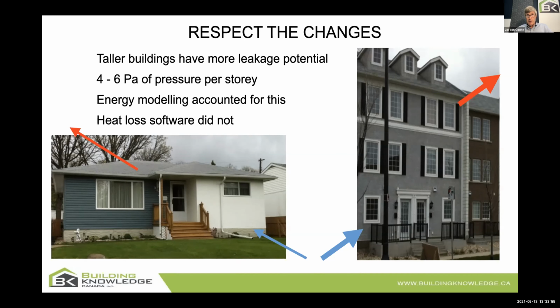Because from a heat loss, heat gain perspective, it makes that building much easier to stay comfortable when I limit that stack effect. And what you need to know is heat loss, heat gain software never used to take this into account. Never used to. And most, let's say the US program, still doesn't take this into account. It does, at least on the residential side. Well, Jason might correct me on that one, but as far as I recall, Manual J does not ask you what floor you're on, but it doesn't adjust based on air leakage. So this is important for us to understand.